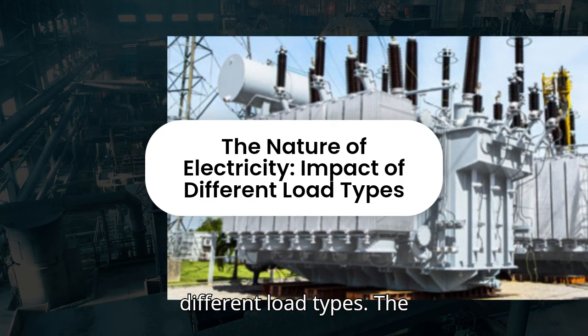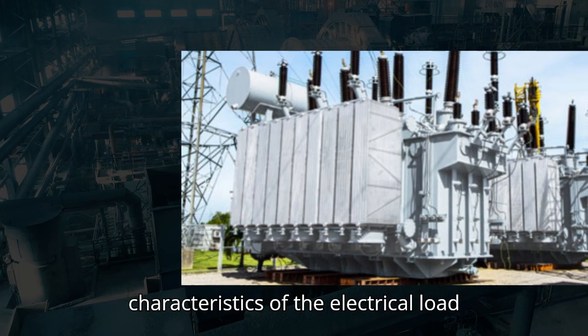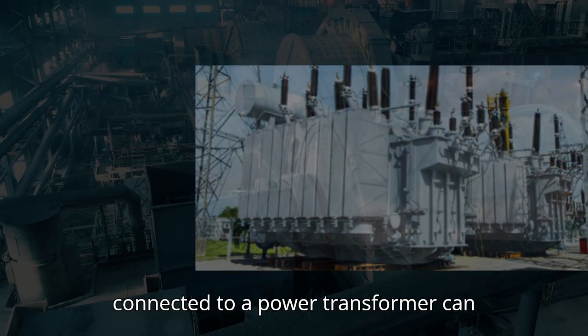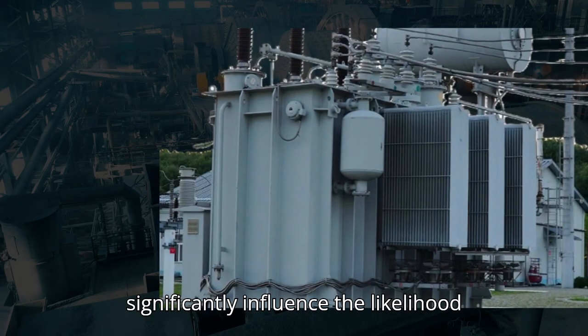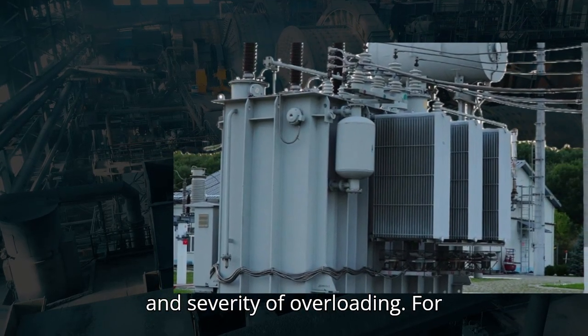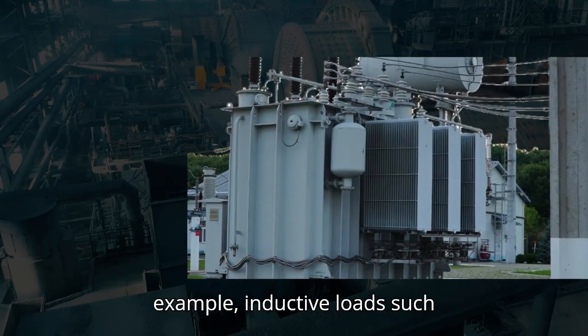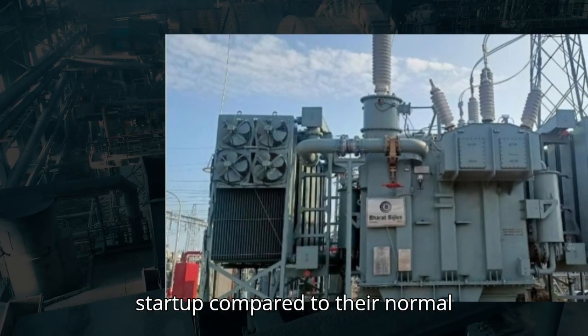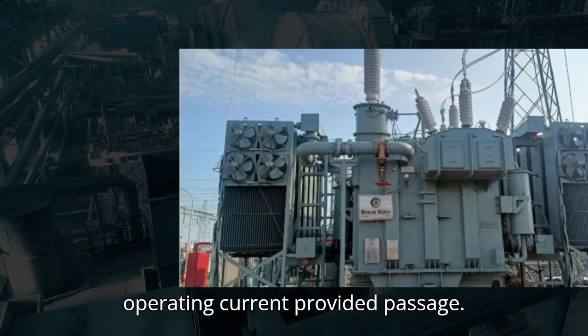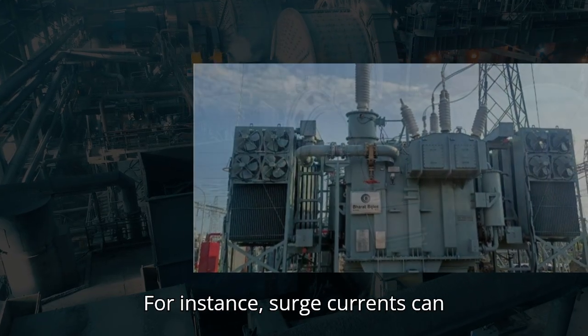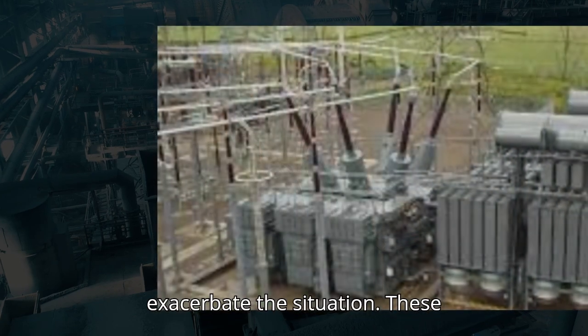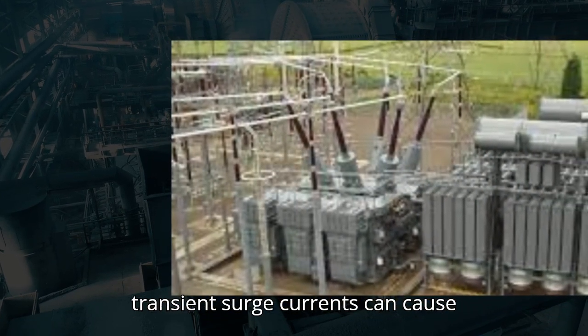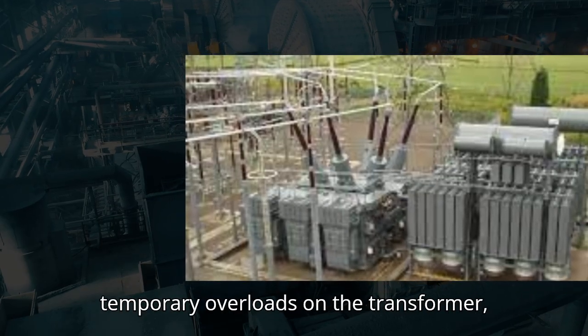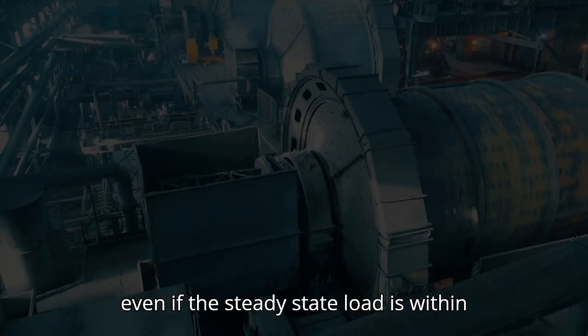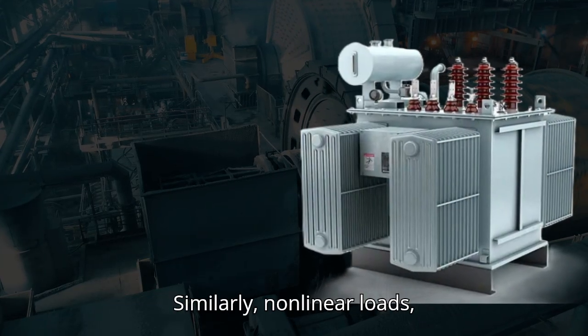The nature of electricity, impact of different load types. The characteristics of the electrical load connected to a power transformer can significantly influence the likelihood and severity of overloading. For example, inductive loads, such as electric motors, often draw significantly higher inrush currents during startup compared to their normal operating current.